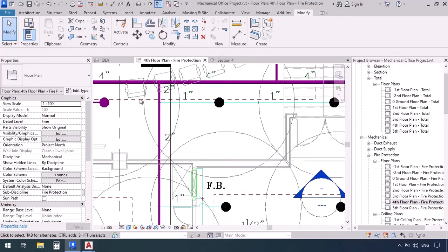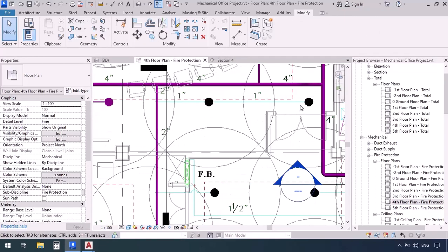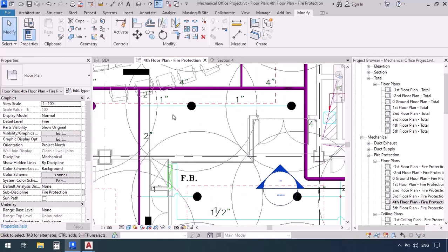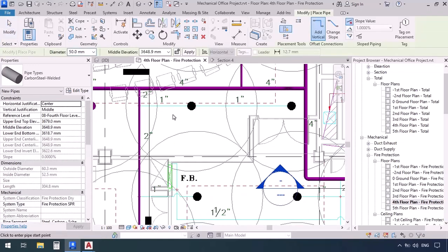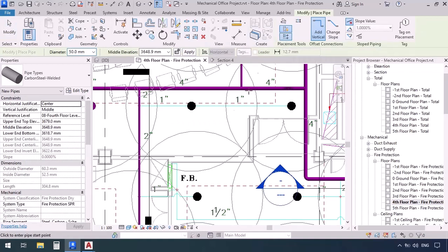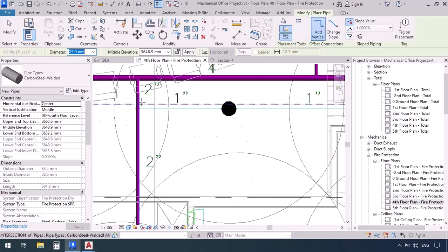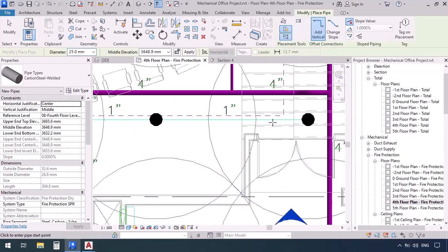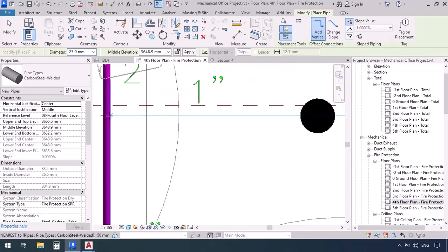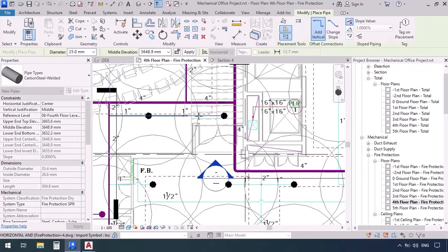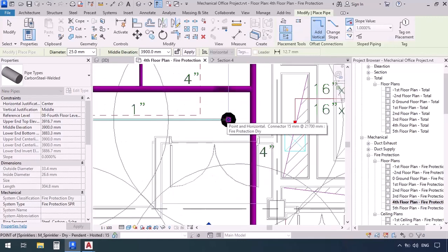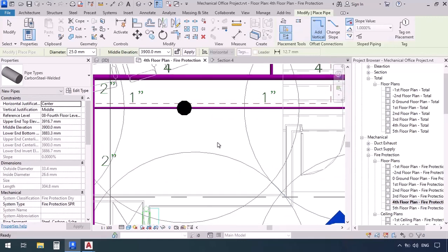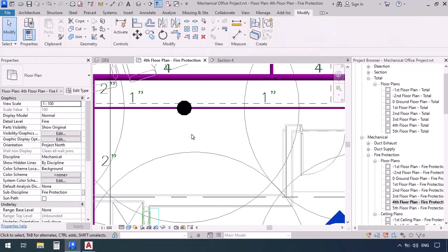Right here we're gonna try to connect these sprinklers. So first the pipe command PI. Once again I can get my junction from the side so I'll use inherit elevation and with diameter 1 inch or 25 millimeters, I'm gonna make a click on the edge of this pipe and then go forward to the second sprinkler and click again to connect them then press escape.